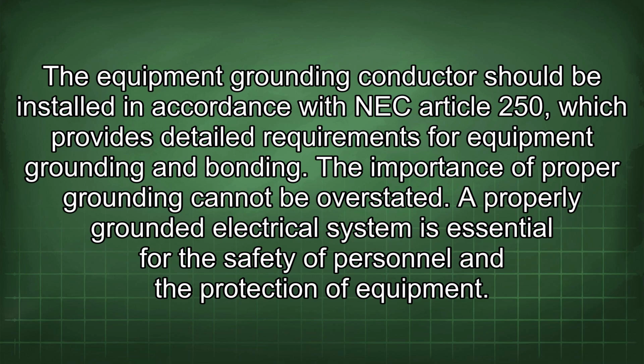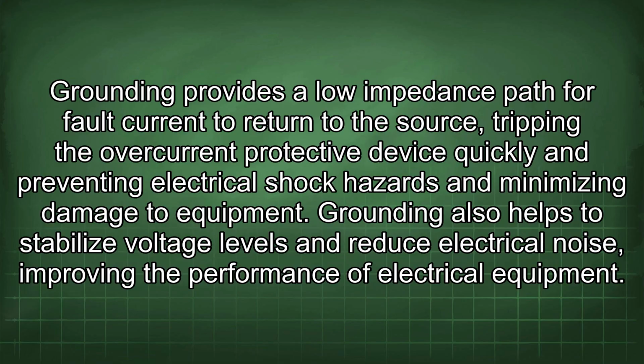equipment grounding and bonding. The importance of proper grounding cannot be overstated. A properly grounded electrical system is essential for the safety of personnel and the protection of equipment. Grounding provides a low-impedance path for fault current to return to the source, tripping the overcurrent protective device quickly and preventing electrical shock hazards and minimizing damage to equipment. Grounding also helps to stabilize voltage levels and reduce electrical noise, improving the performance of electrical equipment.